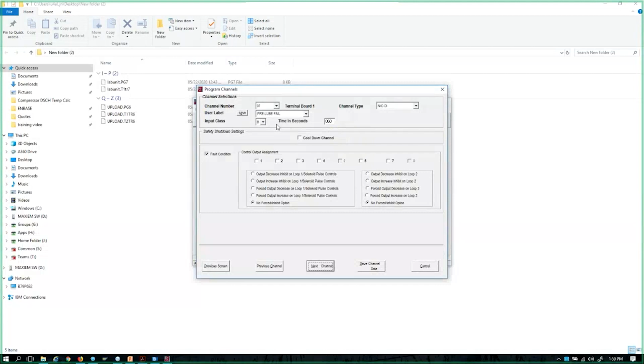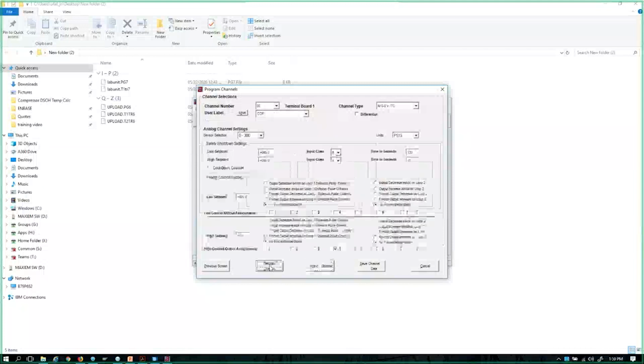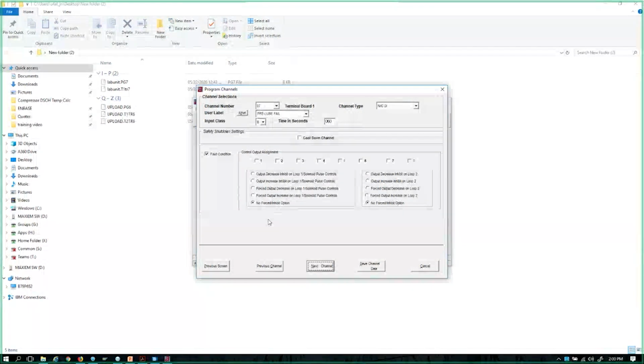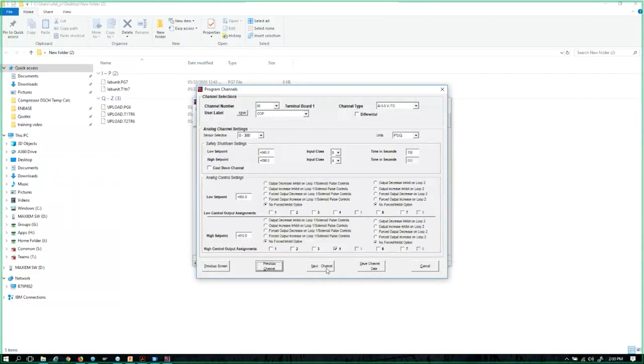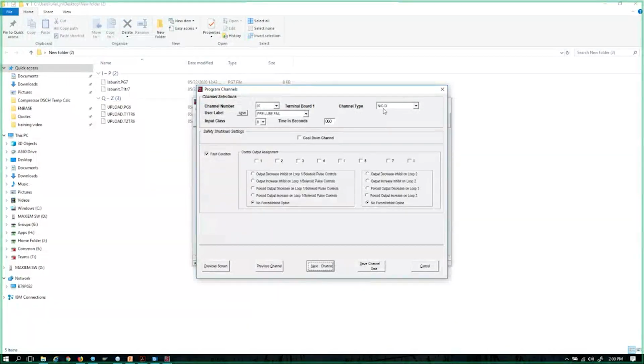Now, remember what we just covered on compressor oil pressure with the B-class timer and the startup sequencing. We kind of reviewed it again. So what we're seeing is, hey, wait a minute. In this case, and I'll kind of cheat a little bit here, we're turning on digital output 4 when the oil pressure is equal to or greater than 10 psi on the compressor oil pressure channel. I'm using that digital output to energize a relay, and I'm closing a set of contacts for channel 7. So channel 7's monitoring this digital output. If this digital output energizes my relay, I know when the contact closes here that I'm okay.